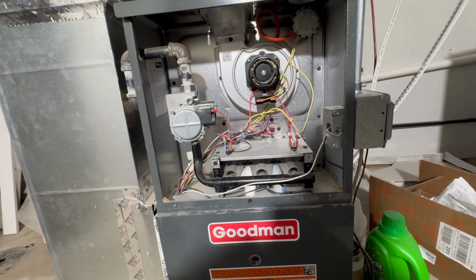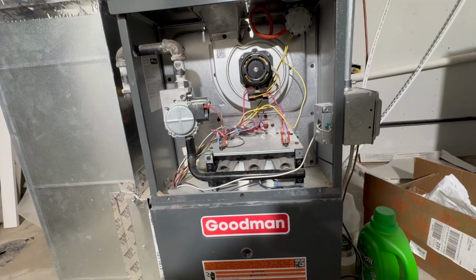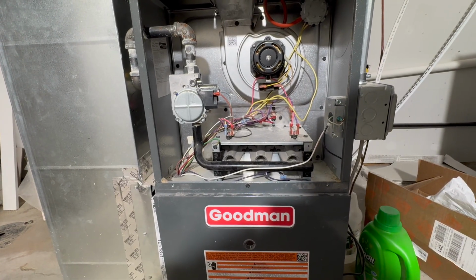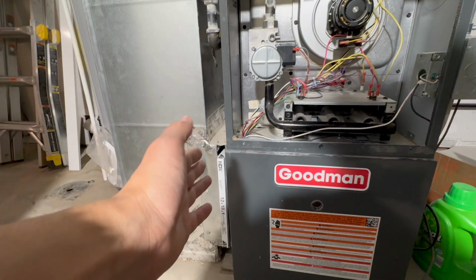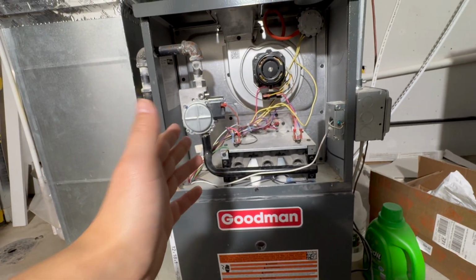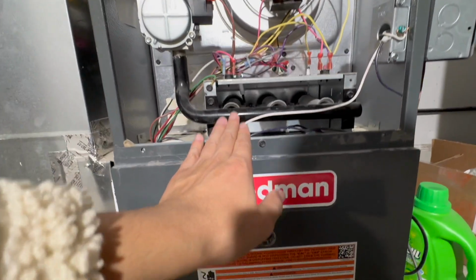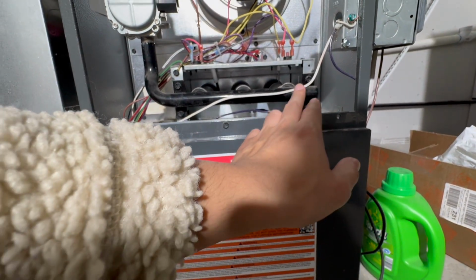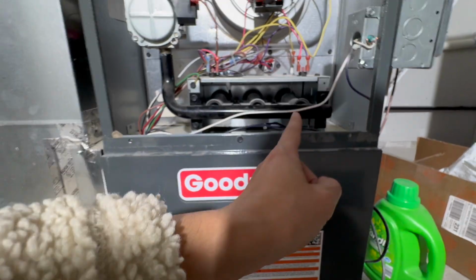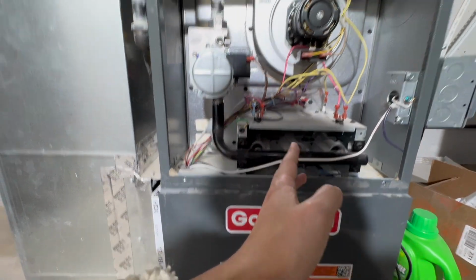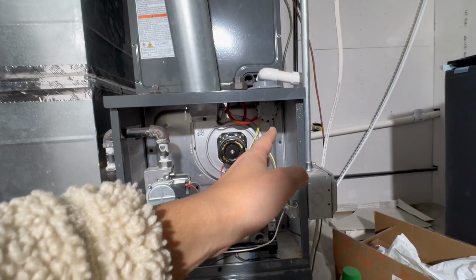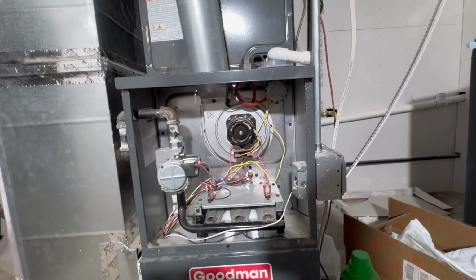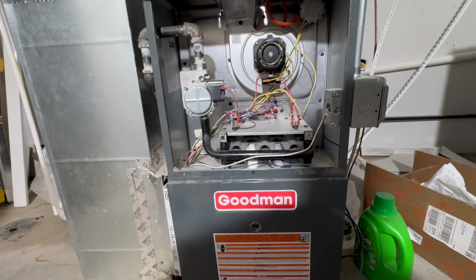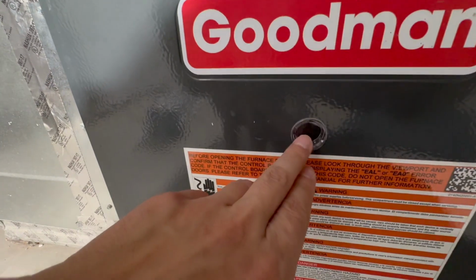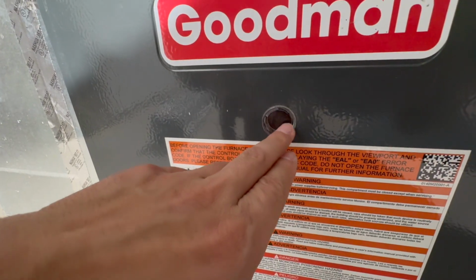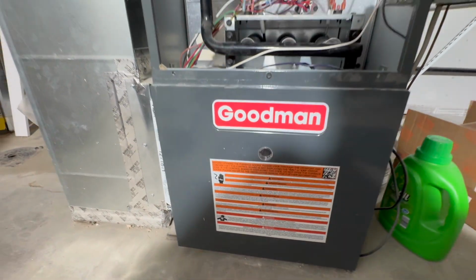It was saying F04. So it's got a lot of things with that. You have to change the filter, check the gas valve, and then the igniter, and then the furnace flame sensor. You check the gas itself, the blower, and inducer, pretty much everything that's connected to the furnace. And you can see the code from here. It was a blinking code. It's a little bit hard to see sometimes.